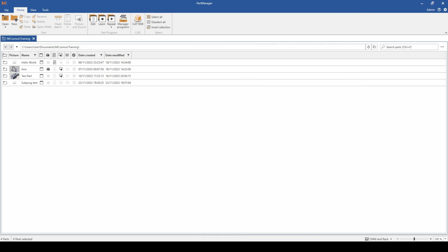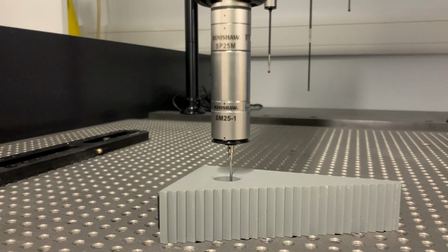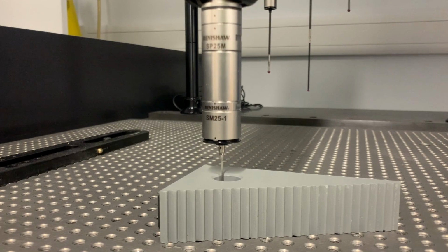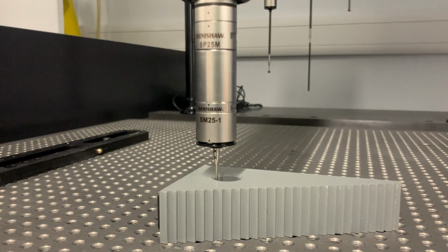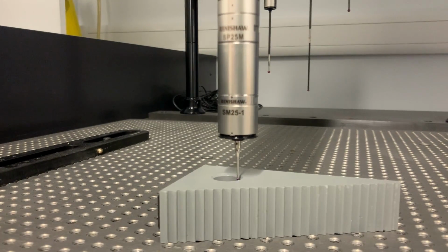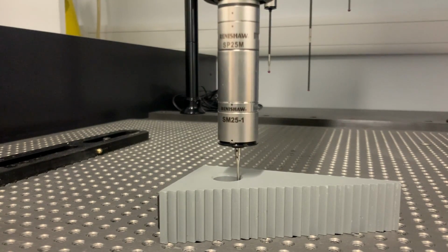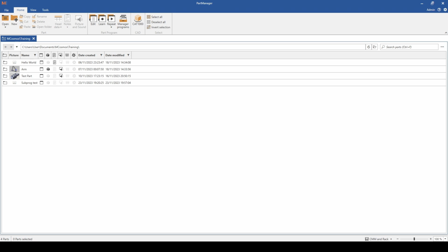If the CMM is using a contact probe, we have 2 ways of collecting probe data. Touch trigger probe: coordinates are obtained when the tip touches a measurement workpiece. It can be used in CNC and manual mode, like TP200 and TP20. And scanning probe: coordinates are obtained while the probe is moving and is in constant touch with the workpiece. And it can be used only in CNC mode, like SP25.